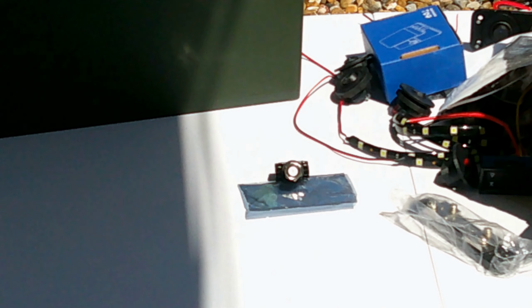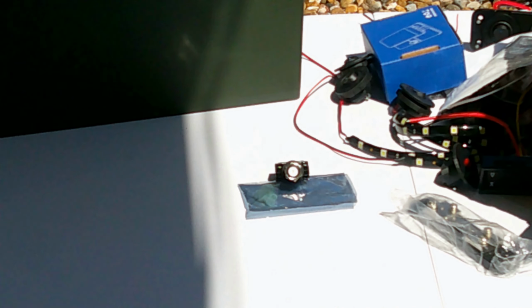Okay, now we're looking at the circuit breaker. This is a 30 amp circuit breaker, so it's really not going to do us much good unless there's some kind of catastrophic direct short circuit or something like that. This will pop, and I have tested it. It does work. I don't know the exact point, but I saw 29 amps, and then the next thing I heard was a pop, and when I looked, the amp meter went to 0. So anyway, it does work.